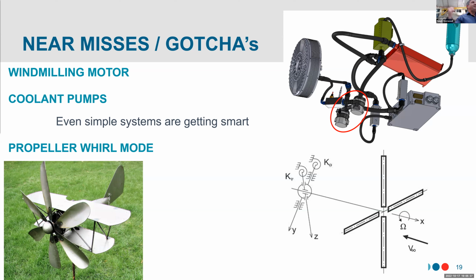The coolant pumps - even simple items are getting smart. These are two 12-volt coolant pumps that circulate glycol. In February, we're flying, the coolant gets cold, and all of a sudden we're getting pressure indications like we have a pump failure in flight. A pump failure is fairly serious to us, so we were getting ready to shut down the propulsion system. We looked into one of our synoptic pages on our display - no, we're still showing pressures, it's just lower. It turns out the pumps are smart.